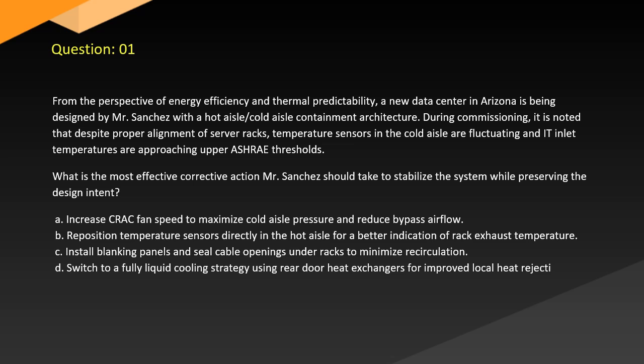Question 1. From the perspective of energy efficiency and thermal predictability, a new data center in Arizona is being designed by Mr. Sanchez with a hot aisle cold aisle containment architecture. During commissioning, it is noted that despite proper alignment of server racks, temperature sensors in the cold aisle are fluctuating and inlet temperatures are approaching upper ASHRAE thresholds. What is the most effective corrective action Mr. Sanchez should take to stabilize the system while preserving the design intent?